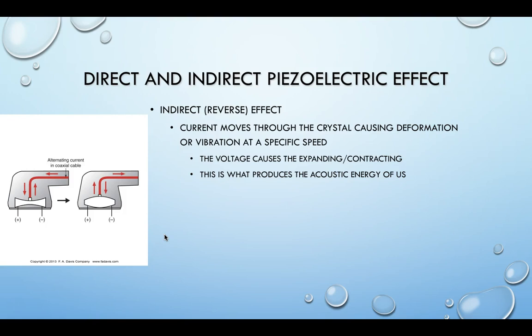What happens is a current moves through the crystal and causes deformation or vibration of that crystal at a very specific speed. We send AC current into the crystal, and that causes the crystal to expand and contract. That expansion and contraction within the capsule — which is the sound head or transducer — pushes air molecules out and in, allowing those molecules to get pushed close together or spread apart. This is how acoustic energy is produced inside the transducer head and then transmitted out through a conducting medium into the tissue.